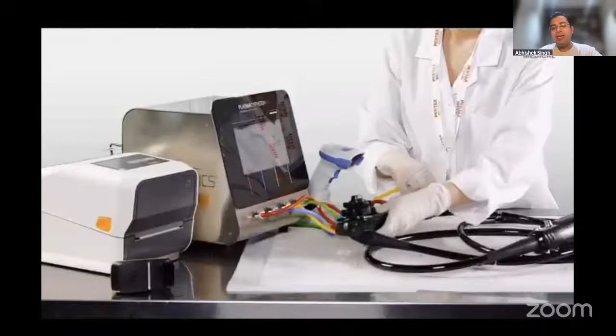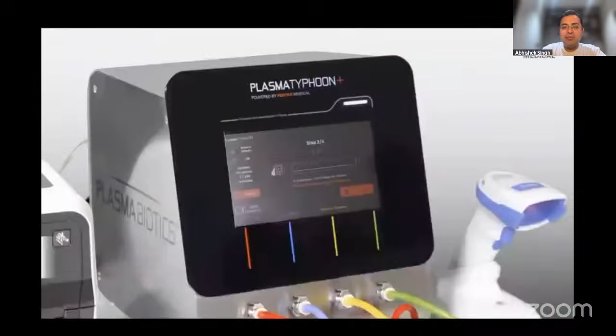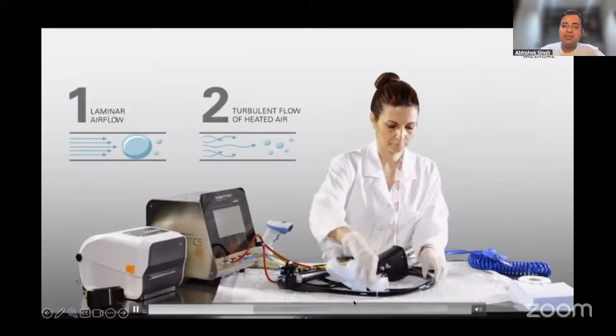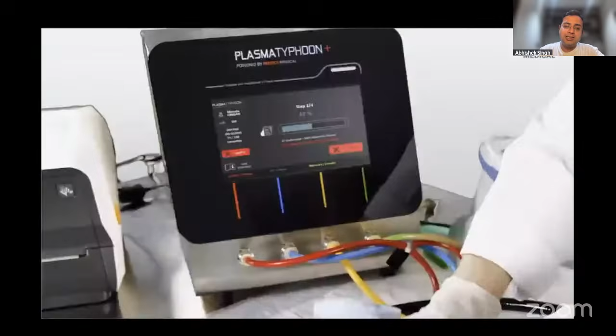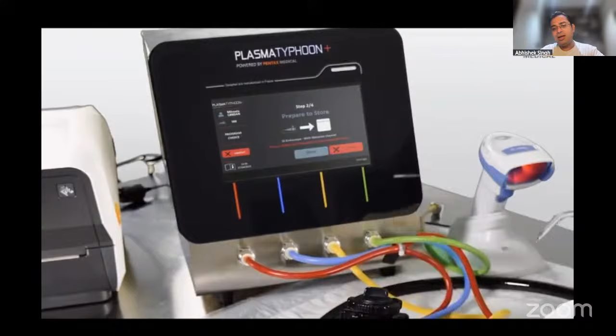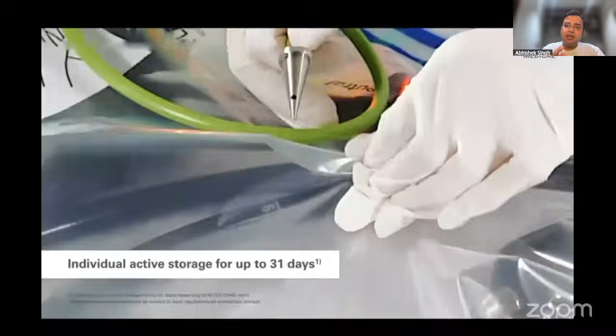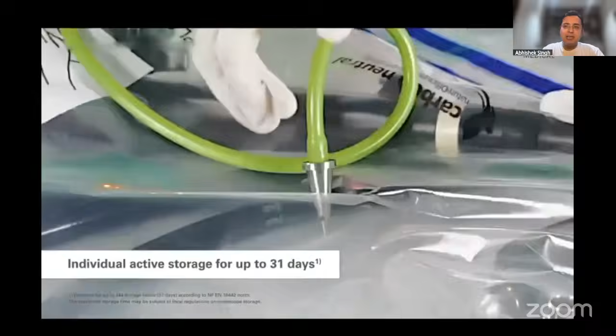Once the instrument is dried and rinsed, part of the pre-cleaning is done. Then there are different color-coded channels that are attached to different channels of the scope. This was classically described for the duodenoscope, and can now be extrapolated to flexible ureteroscopes. You connect them to the channels, give them their gestational time, and within a period of 3 to 5 minutes, pre-cleaning can be done.